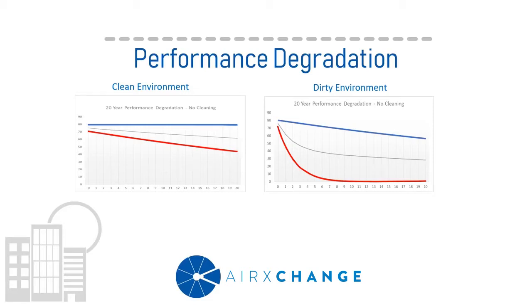So as the device gets dirty over time, the first thing you're going to notice is that you aren't transferring as much water vapor. And in most buildings and in most cases, humidity is a big concern. Another thing to take into consideration as a device gets dirty is it starts to block some of the airflow, which not only places a burden on trying to deliver the code required ventilation, but also places a structural burden on the component due to the higher pressure drop. The higher pressure drop will then result in greater fan energy use. So you can see how we're building a case where all these components are interrelated.